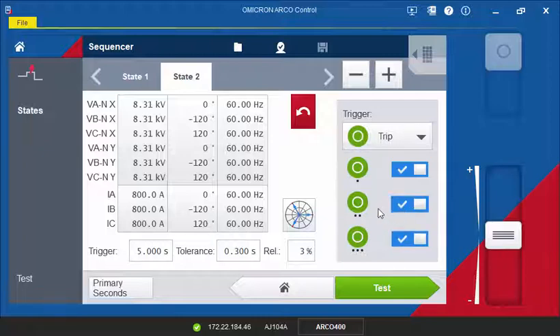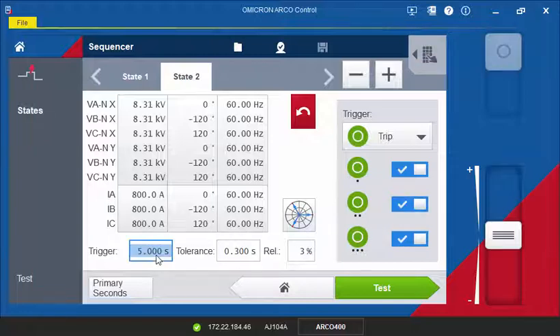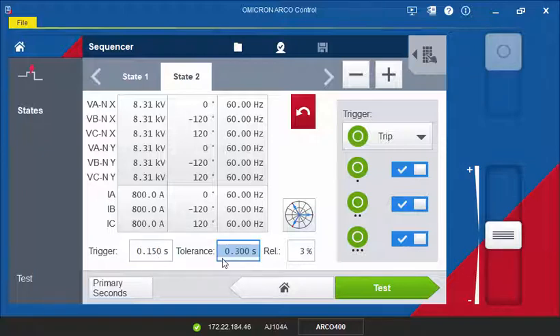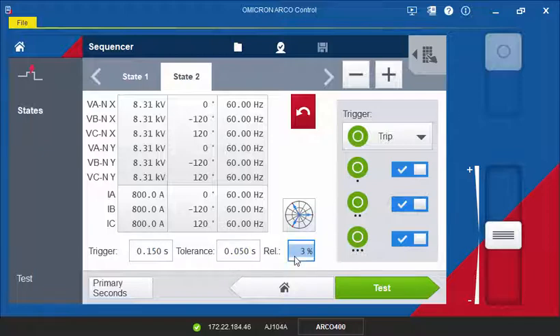To complete the configuration of the fault state, we will now have to enter the expected trip time together with the absolute and relative tolerance values. These values will be used to assess the trip time. If there is no trip during the defined trigger time, including the defined tolerance, the test will abort.